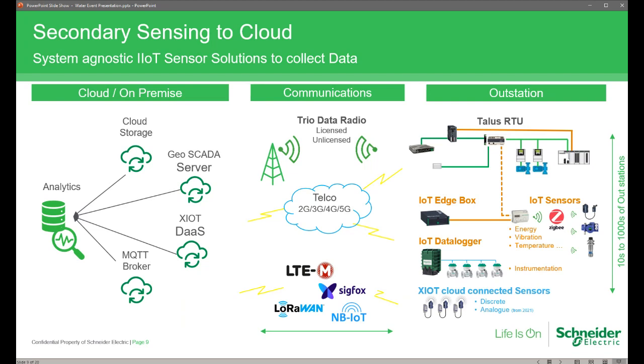We're also seeing instances of MQTT brokers being deployed instead of more traditional database storage solutions. These allow SCADA, telemetry, and analytical solutions to register interest on topics and receive data when the broker receives data from site. This provides great flexibility for the end user, allowing them to decide what data is consumed by which solution. One of the defining characteristics of solutions adopting IoT technologies such as MQTT and low-power WAN is the lightweight communications. As a result, some of these low-power, often battery-operated devices can actually run for years — and in some instances over a decade — transmitting data.